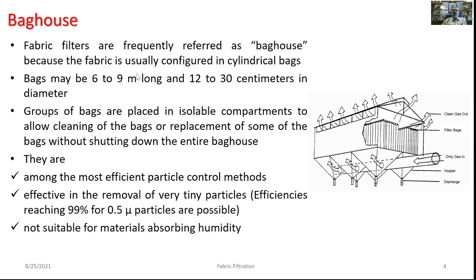Fabric filters are referred to as baghouses because a house-like assembly accommodates an assembly of cylindrical bags. These bags could be 6 to 9 meters long with a diameter of 12 to 30 centimeters. This group of bags is placed in isolable compartments to allow cleaning or replacement of some bags without shutting down the entire baghouse. Baghouses are among the most efficient particulate control methods, capable of removing particles as small as 0.001 micron.